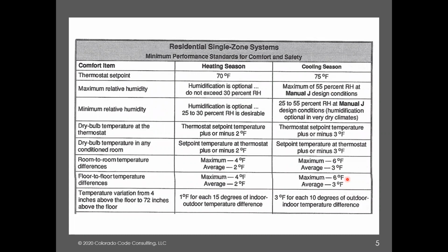Hopefully I told you that story about the temperatures that we set around the place. And we had really high temperatures that year. It was 105 degrees outside. Well, believe me, there was a 10-degree difference between the first floor and the second floor, easy on those days. And the system was working exactly how it was designed, okay? So just because it's a little warm upstairs doesn't mean the system wasn't working. It works just exactly the way they designed it.